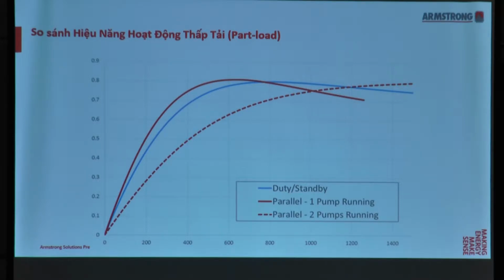Next, this graph basically shares the part load efficiency comparison between a duty standby, which is the curve in blue, versus parallel pumps, whether it is 1 pump running or 2 pumps running. You will realize that in this small portion, a duty standby gives you a better efficiency, but in terms of the overall, you will see that the red curve, which is the parallel pumps, has much higher efficiency compared to duty standby at part load.